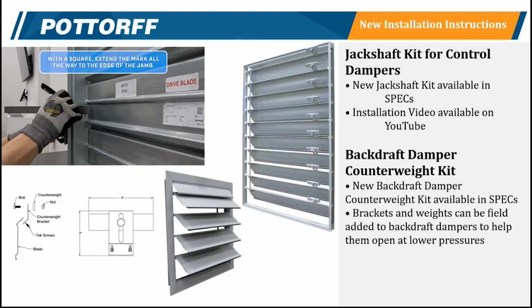Another kit that's been requested by our customer service group for a long time is our backdraft damper counterweight kit. Right now in specs, if you have a backdraft damper that wasn't ordered with counterweights initially, say a BD150 or BD250, you can order this counterweight kit and add them in the field. These counterweights help the dampers open at a lower pressure and lower velocity than a standard BD150 or BD250.